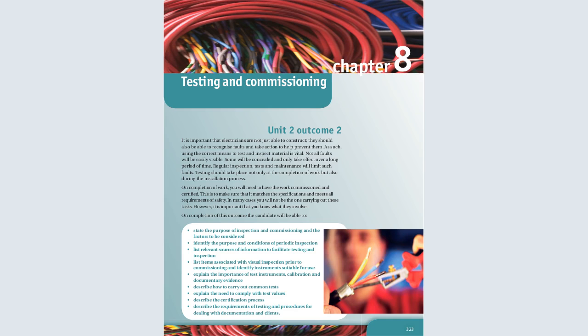So it is important that electricians are not just able to construct, they should also be able to recognize faults and take action to help prevent them, such as using correct means to test and inspect materials. It is vital. Not all faults are easily visible, so some will be concealed and only take effect over a long period of time. So regular inspection, testing, and maintenance will limit such faults.